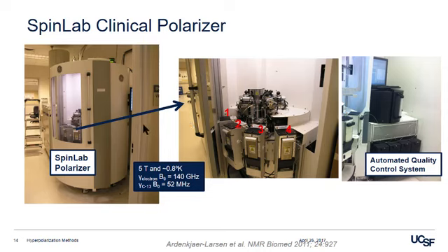And that diagram is from an older system. This is the modern clinical use system where you can polarize 4 samples, do quality control, little higher field and lower temperature, boosting polarization as well.